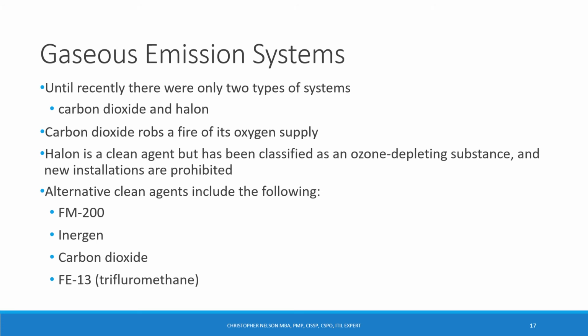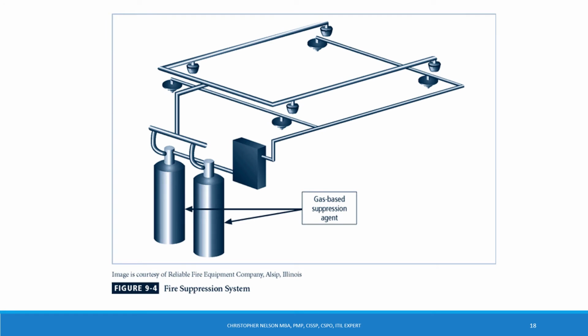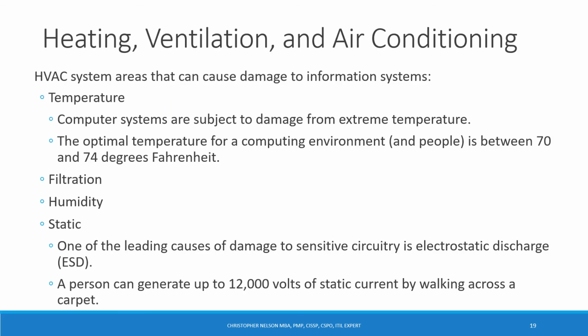For gaseous emission systems, you have carbon dioxide, which robs the fire of its oxygen supply. Alternative agents include FM200, Inergen, carbon dioxide, and Fe13. Halon is a clean agent but has been classified as an ozone depleting substance, and new installations are prohibited from using it. A fire suppression system has a gas-based suppression agent. HVAC systems can cause damage to information systems. The damage can come in the form of temperatures, filtration, humidity, or static.